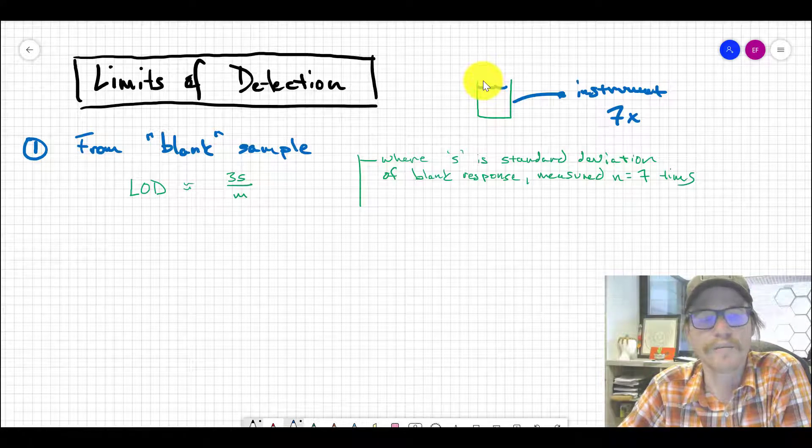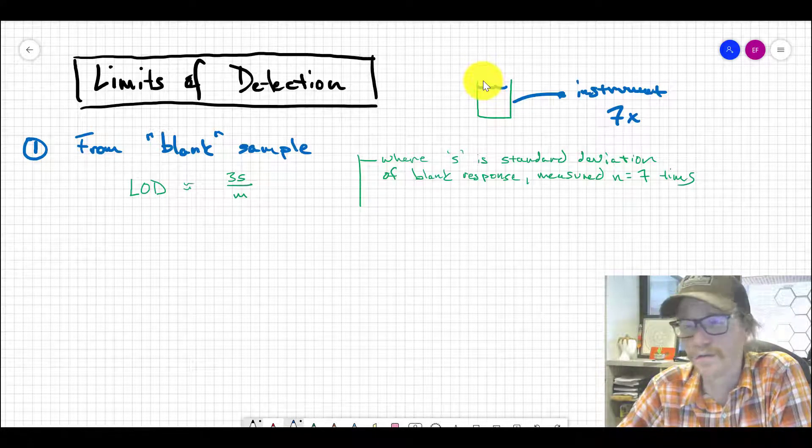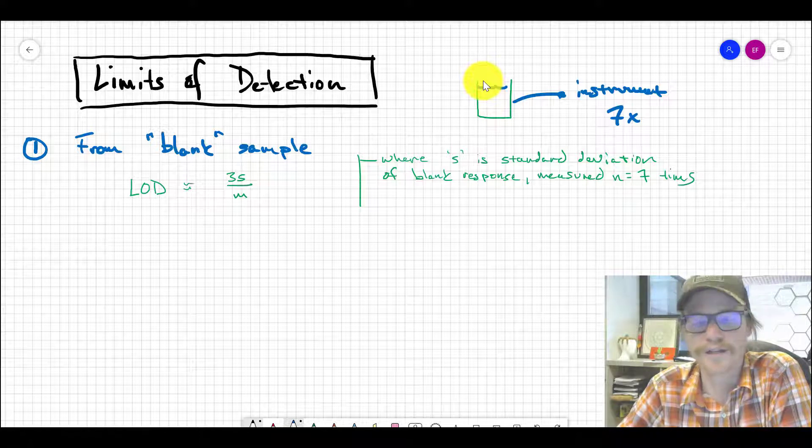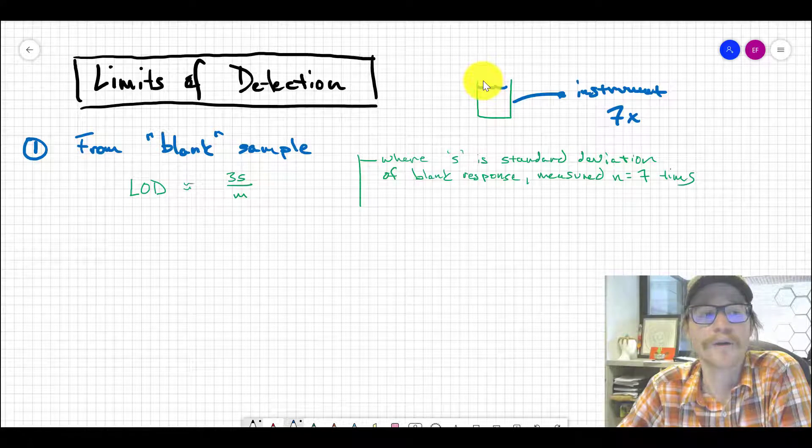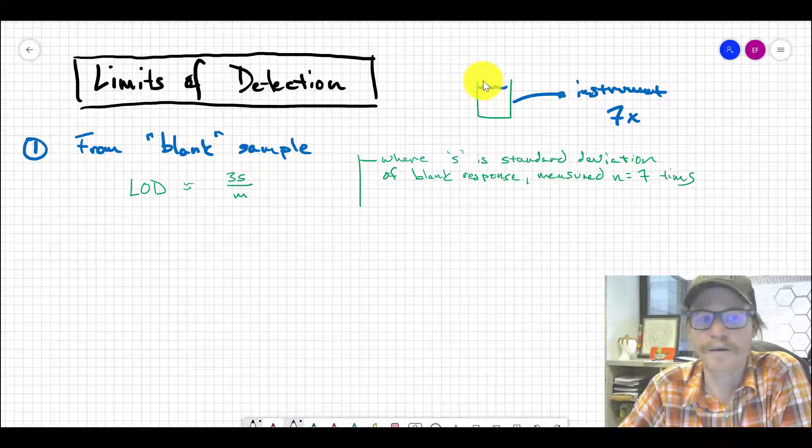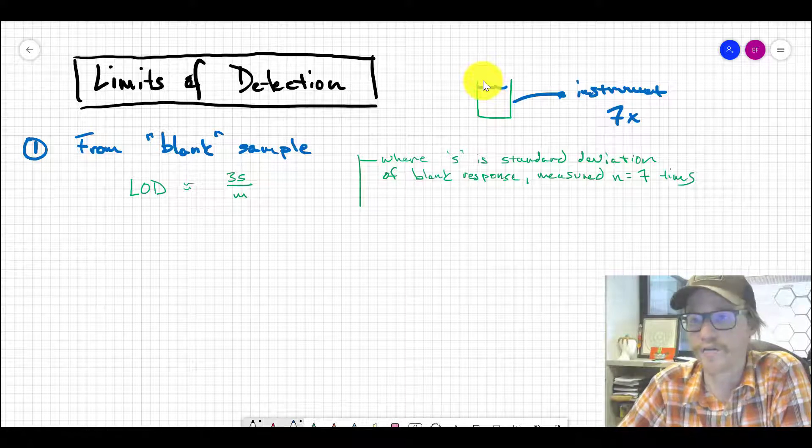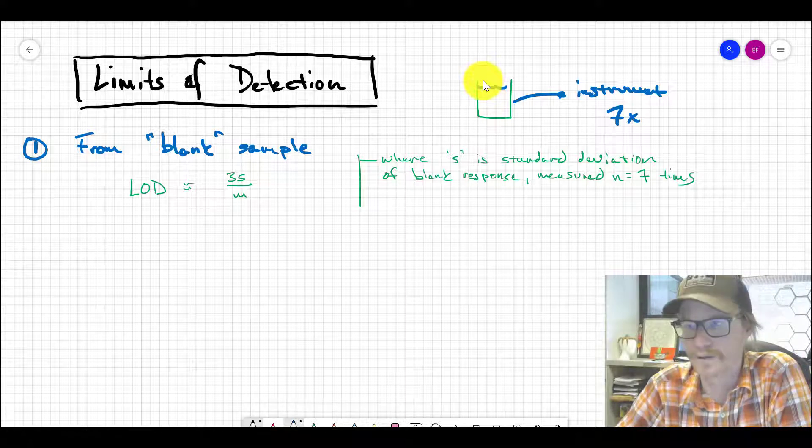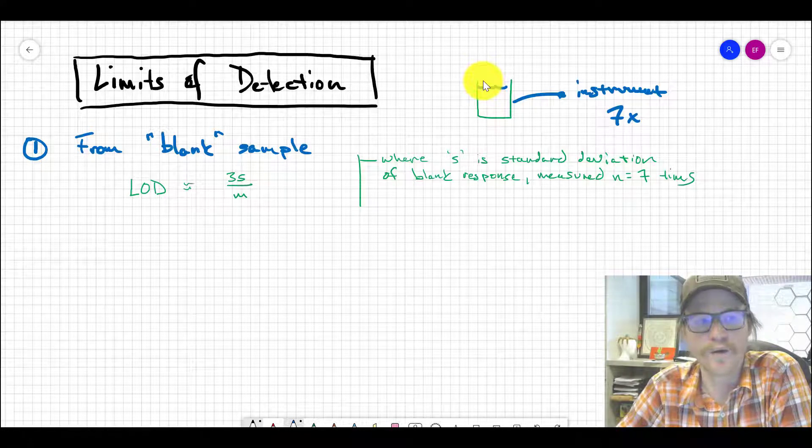The limit of detection is three times the standard deviation in whatever the response units are. So if it's absorbance, you take the standard deviation of absorbance values times three, then divide by M, the slope of the calibration curve. That's the basic way to measure LOD using a blank sample measured seven times.